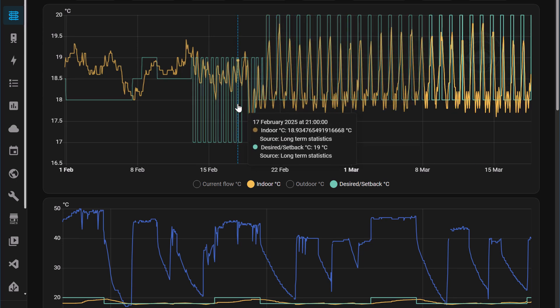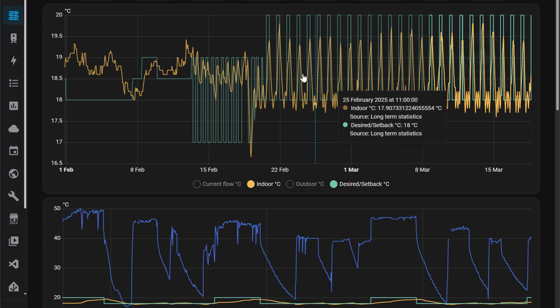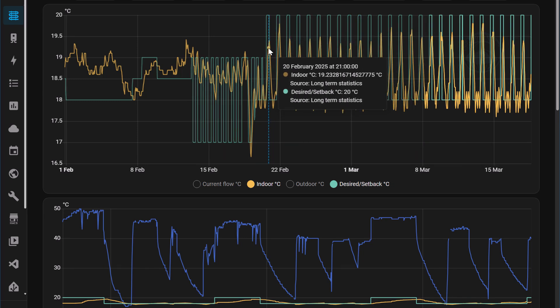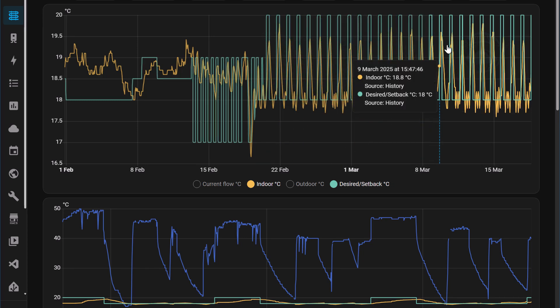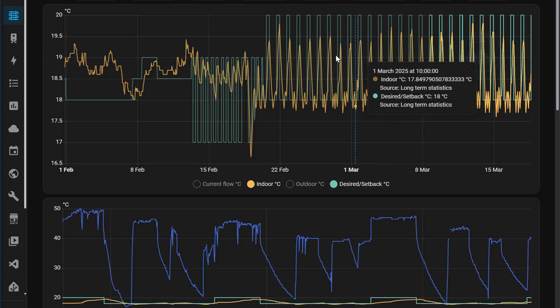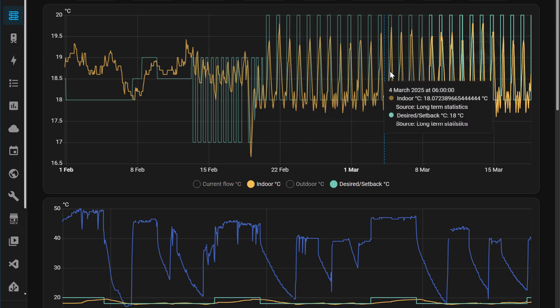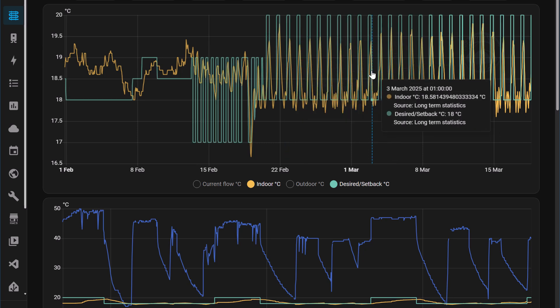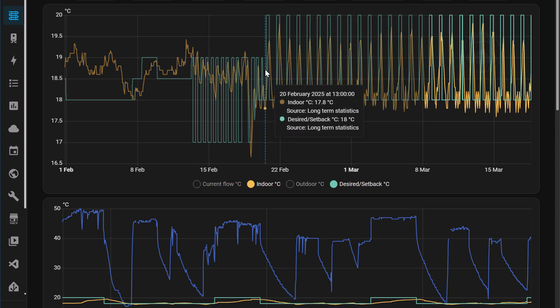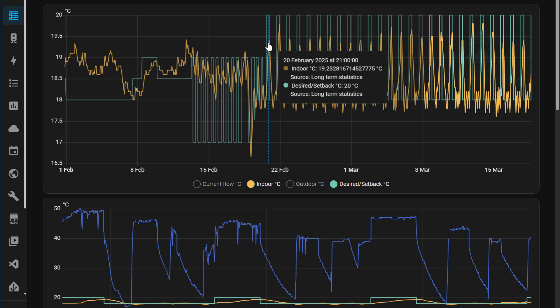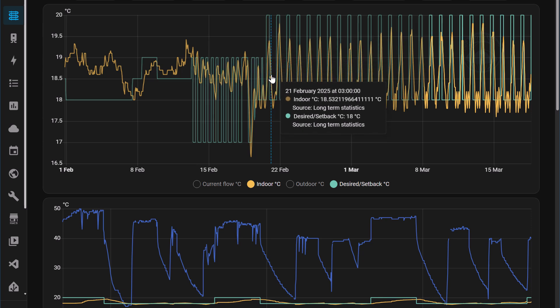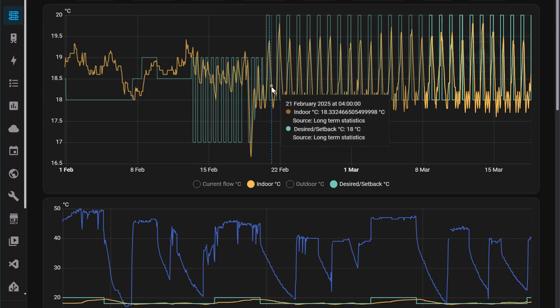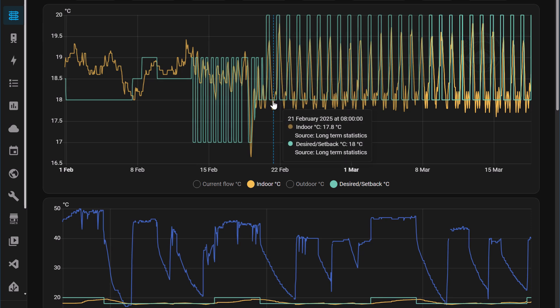And here you go. Yeah, you can see that I've basically been maintaining this constant temperature throughout this time. Now, the way this expanded works is, so obviously I'm not reaching the desired temperature in the timer. But then when the timer is off, the boiler turns off as well. And you can see that the indoor temperature then starts to drop off and drop off and drop off. And once it's dropped through the setback temperature by either 0.2 or 0.4, that's when it turns back on, the boiler turns back on.